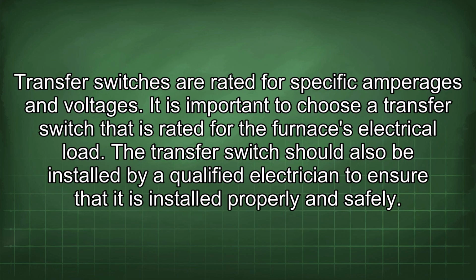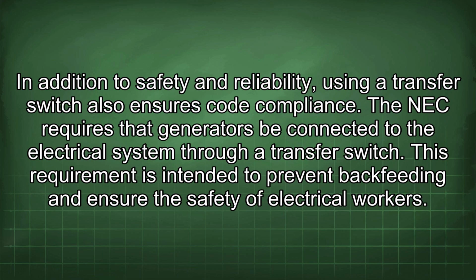Transfer switches are rated for specific amperages and voltages. It is important to choose a transfer switch that is rated for the furnace's electrical load. The transfer switch should also be installed by a qualified electrician to ensure that it is installed properly and safely. In addition to safety and reliability, using a transfer switch also ensures code compliance. The NEC requires that generators be connected to the electrical system through a transfer switch.